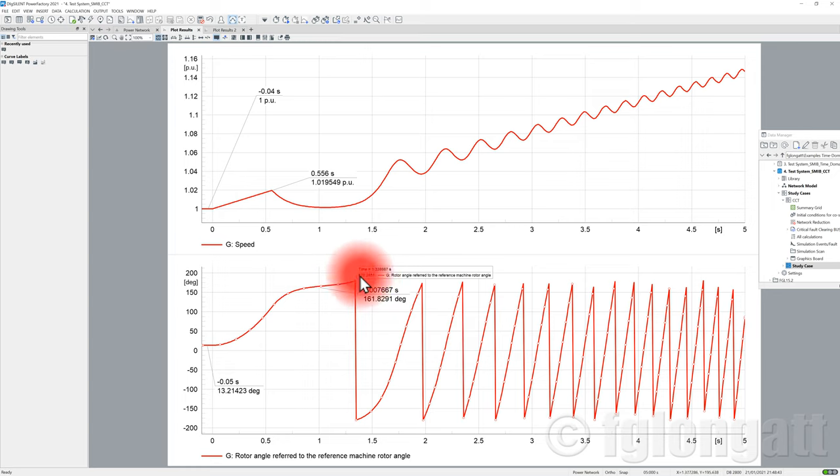And you can see how the angle is still increasing, and you can see here how the rotor speed is increasing. To be honest, in terms of this specific behavior, you can see that there are some oscillations, but those oscillations are slightly damped. But the problem is that we have here a non-oscillatory unstable condition. Because even though those small oscillations are dissipating, we have here a component that is making the rotor angle and also the rotational speed increase very, very fast. And this is the case where I can tell you this is a fully rotor angle unstable system, okay?